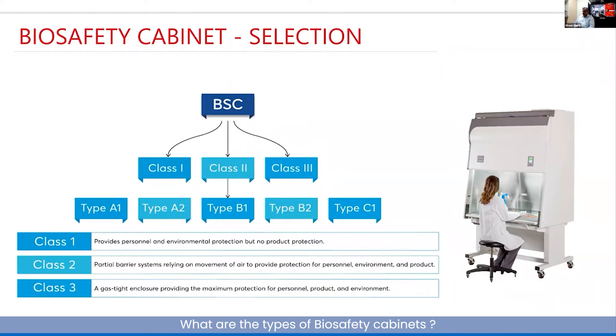As far as Class 1 is concerned, it provides personal and environmental protection, but the product is not protected. The sample you're working with can potentially get contaminated with outside air. As a result, Class 1 is more or less obsolete now.